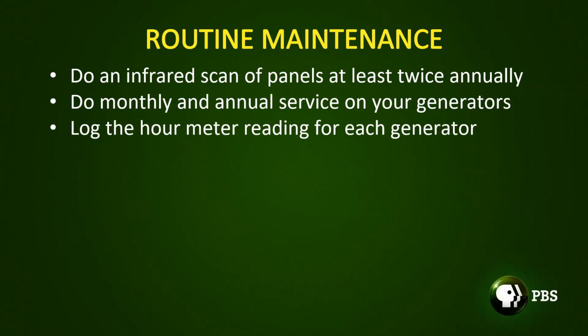The third is to log the hour meter reading for each generator each week. This might seem unnecessary, but do you really know how much your generator ran? It may have started and run for a while, particularly on a remote site, without you being notified, whether it should have notified you or not. So you need to keep track of how much mileage you've put on each generator. One of the first questions a manufacturer will ask if you call seeking advice is, how many hours are on that unit? It's nice to know.